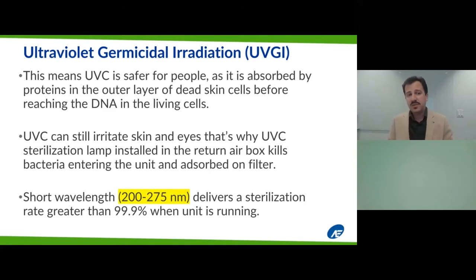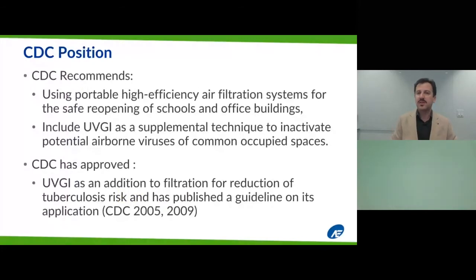They can still irritate skin and eyes, and that's why UVC sterilization lamps are installed in the return air boxes to kill bacteria entering the unit or possibly absorbed by the filter. We know that the short wavelength of 200 to 275 nanometers can deliver a sterilization rate of around 99.9% when the unit is running, and that is great. But let's see the regulatory bodies' position on these technologies. The CDC, or Centers for Disease Control and Prevention, has recommended using portable high-efficiency air filtration systems for the safe reopening of schools and office buildings. They also recommend including UVGI, or ultraviolet germicidal irradiation, as a supplemental technique to inactivate potential airborne viruses in commonly occupied spaces.